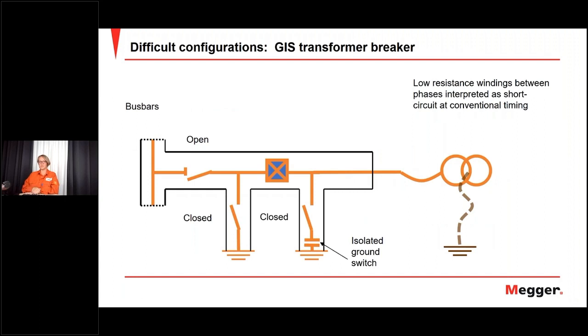breaker. Also, another GIS here, where you have a transformer which is directly connected on the right side. To measure this the classical way, you would have to remove the slack here on the transformer. And that's always a risk, of course, not to get it properly placed again. And it's not always so easy. It can be quite a lot of screws and details. But with dual ground, we can measure this without removing any mounted parts.